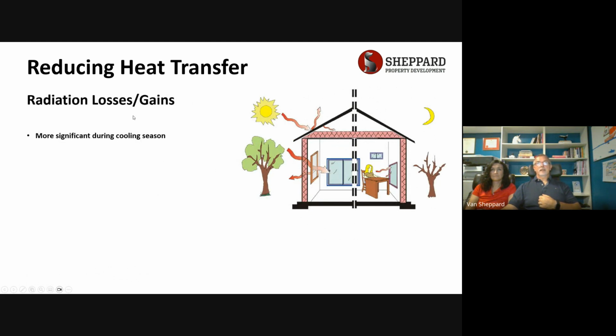So the last means of heat transfer is radiation loss, and it's more significant during cooling season than it is during the heating season. That's primarily because the amount of solar heat gain you get in your building is how you size your air conditioning system. So the better job you do of reducing solar heat gain, the smaller your air conditioning system can be, and that affects the energy consumption, which means the smaller your mechanical systems, the smaller your solar array needs to be to achieve net zero. So it's primarily sunlight through exposed windows.